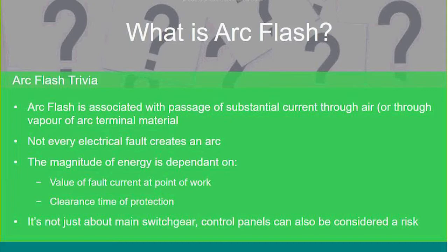And the magnitude is dependent upon the fault current at that point in the distribution system. So logic tells you at main low voltage terminals on the output of transformers, the fault current is normally significant, and you tend to find in these particular instances the risk associated with working in and around that zone in a switchboard is very high because of the very nature of the fault current. By the time you get down into final subcircuits, the energy levels are considerably smaller, and therefore the level of energy is reduced. However, there's another parameter that we need to consider, because it's also dependent upon the time taken to clear that fault.